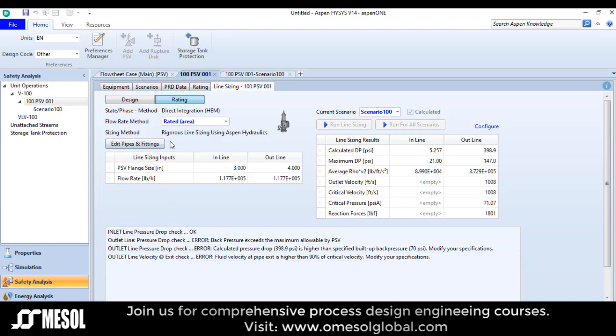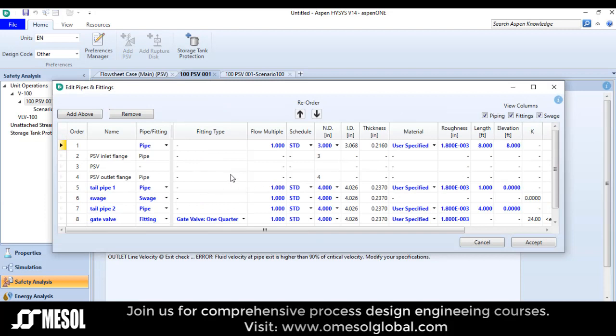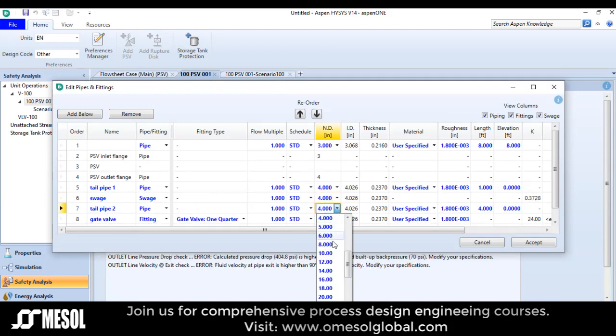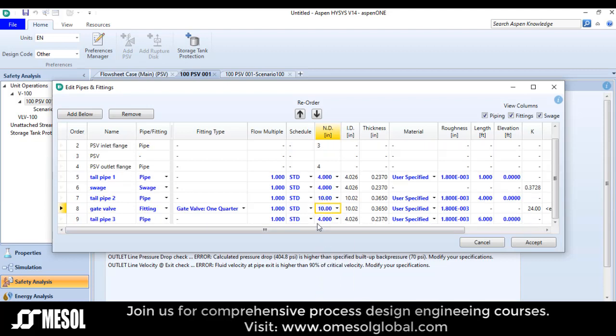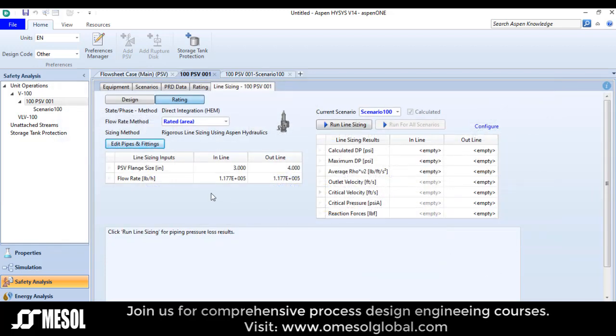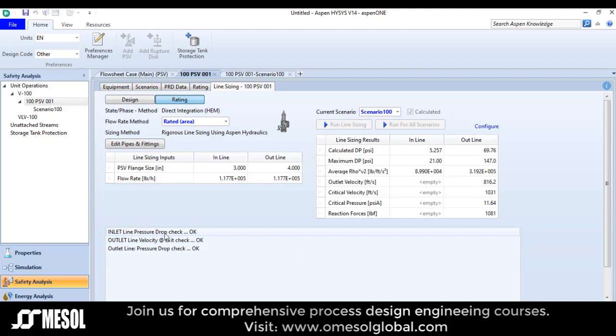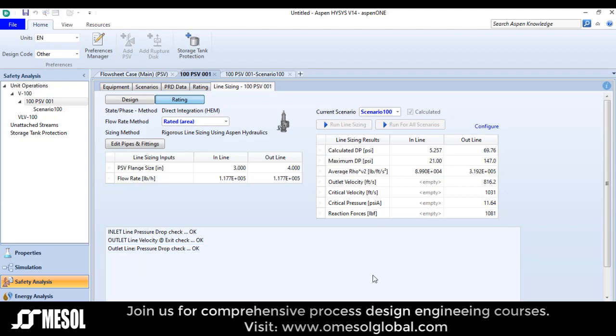In this particular case I will go to 'edit piping and fitting'. Tailpipe 2 is changed to 10 inches and tailpipe 3 is also changed to 10 inches. Now I will run the scenario again. You can see that the inlet line pressure drop check is OK, outlet line velocity check is OK, outlet line pressure drop check is OK. It is successfully completed.